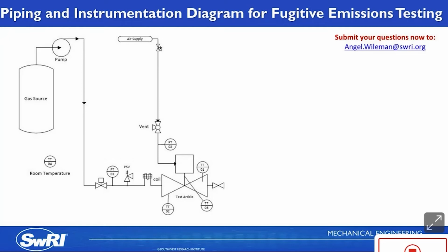The coil that's shown upstream of the valve is intended to go inside the thermal enclosure, and this helps lower or raise the gas temperature before entering the valve. And thermal control isn't shown on this P&ID, but the entire valve assembly will need to be enclosed to bring the valve to temperature during thermal cycles, with the actuator outside of the enclosure. We have a PSV, which is a pressure safety valve, installed upstream of the valve, and this protects against overpressurization. Make sure you consider the rating of the valve, the rating of all other components whenever you're selecting the PSV set pressure. And the diagram shown here assumes that this valve would be an air-actuated valve, so you need an air line running to it, with a 3-way valve so you can remotely control the cycles of the valve, and also a pressure transducer that can be used to measure the torque required to actuate the valve during testing.